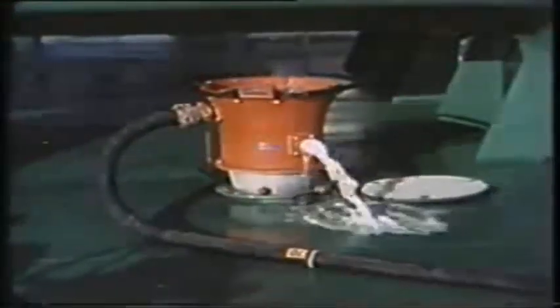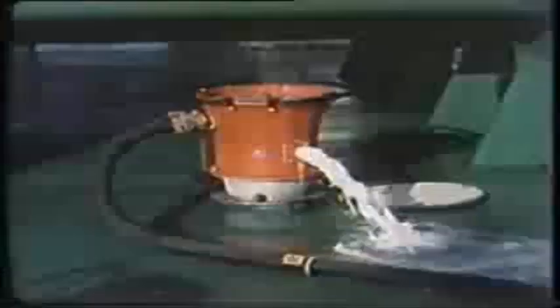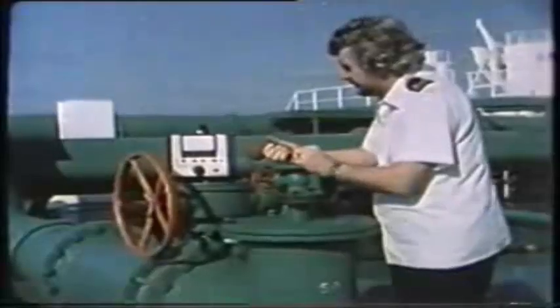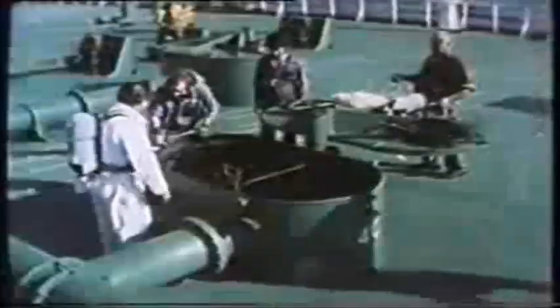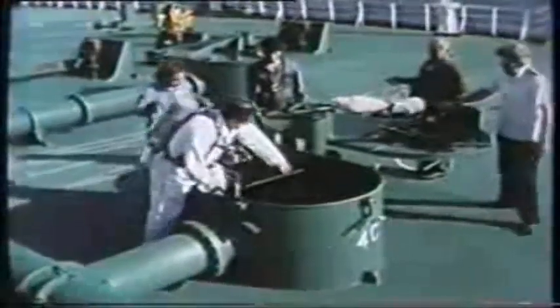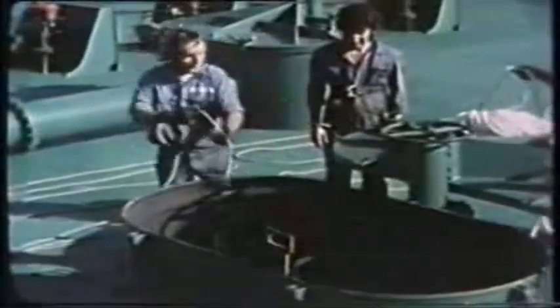A lot of maintenance is carried out on inerted ships, but for repair work inside tanks they must be thoroughly ventilated first. Gas freeing can be done in two ways: with portable fans or with the IG system blowing air. For the first method, the individual tank is locked open, isolated from the IG main, and portable fans are mounted in the tank washing apertures either to suck out the IG or to blow in fresh air. During this exercise the tank atmosphere must be carefully monitored. When oxygen gets back to a normal 21 percent and the hydrocarbon reading on the explosimeter is zero, the tank can be entered. The first man in must take breathing apparatus and an analyzer to check the remote parts of the tank, and the portable fan should be kept running to disperse any hydrocarbon vapor released from disturbed scale or sludge.